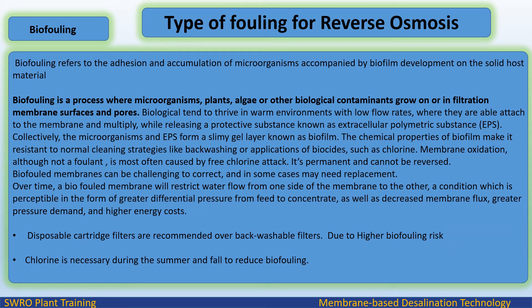Biofouling refers to the adhesion and accumulation of microorganisms accompanied by biofilm development on the solid host material. Biofouling is a process where microorganisms, plants, algae, or other biological contaminants grow on or in filtration membrane surfaces and pores. Biological organisms tend to thrive in warm environments with low flow rates, where they are able to attach to the membrane and multiply, while releasing a protective substance known as extracellular polymeric substance (EPS).